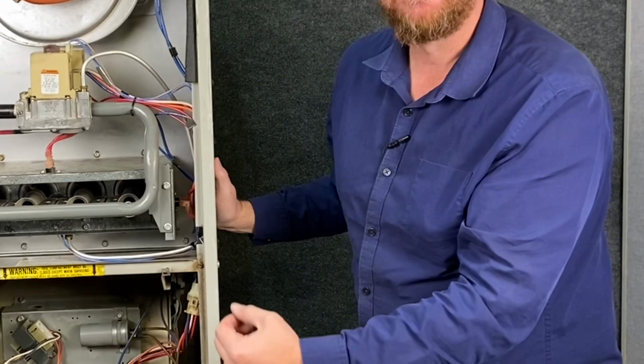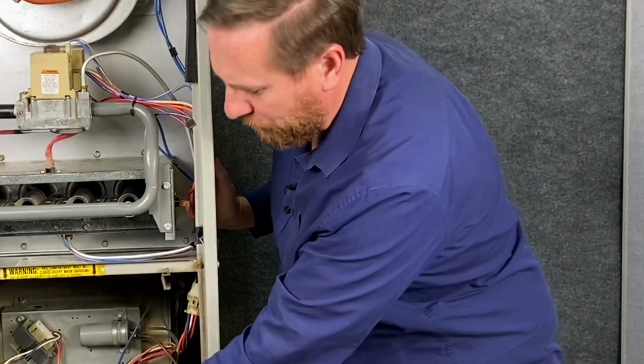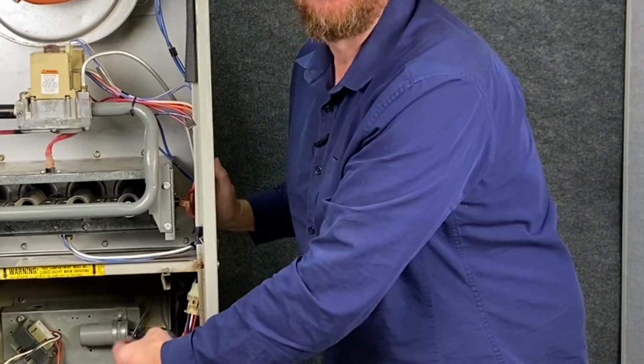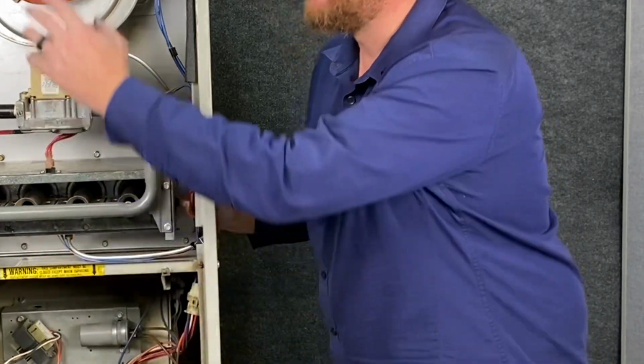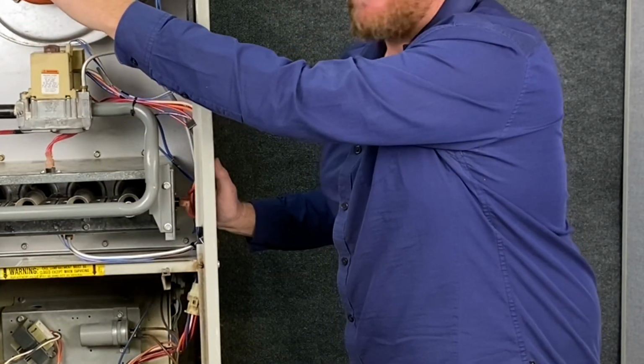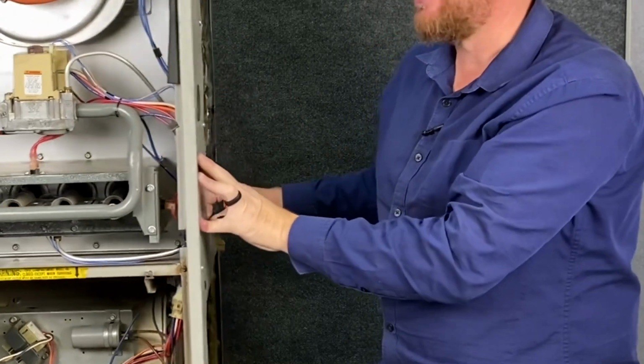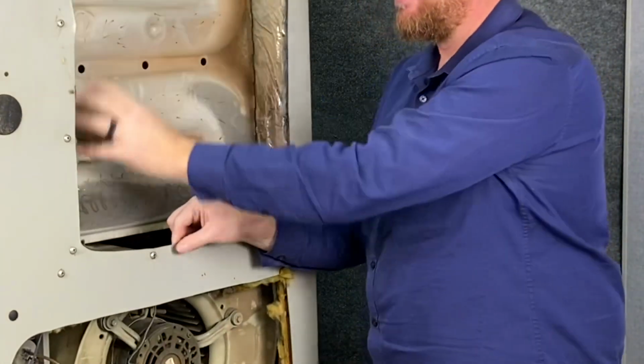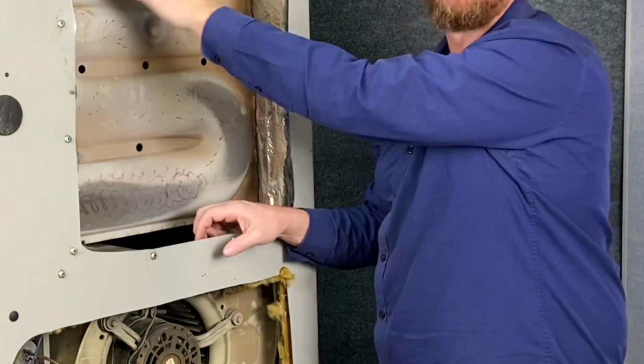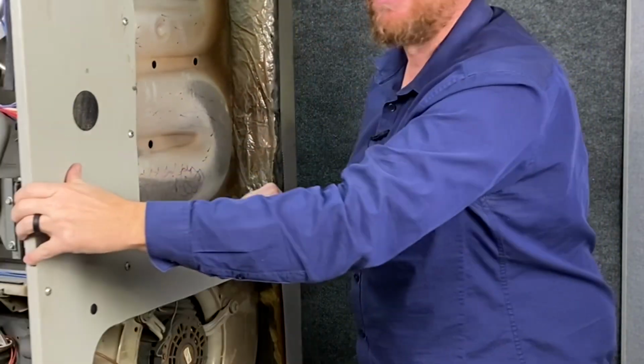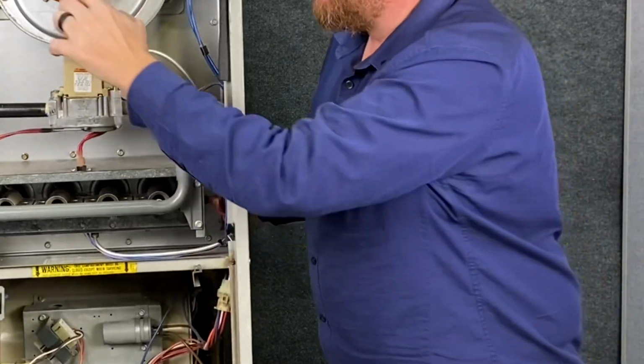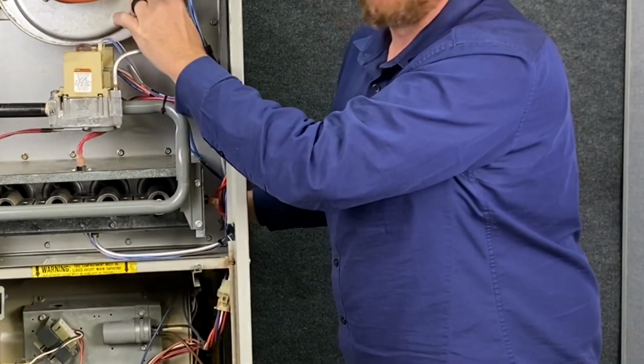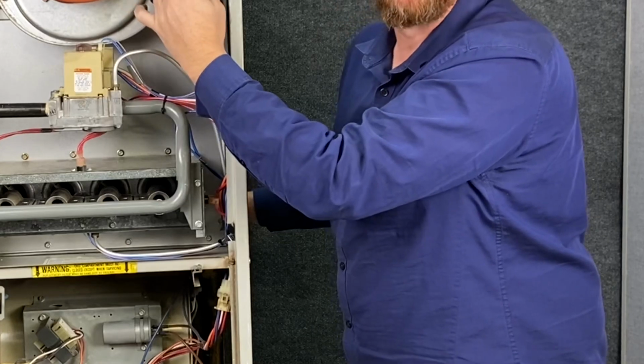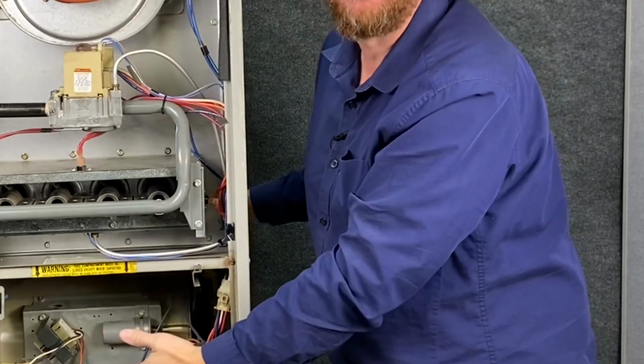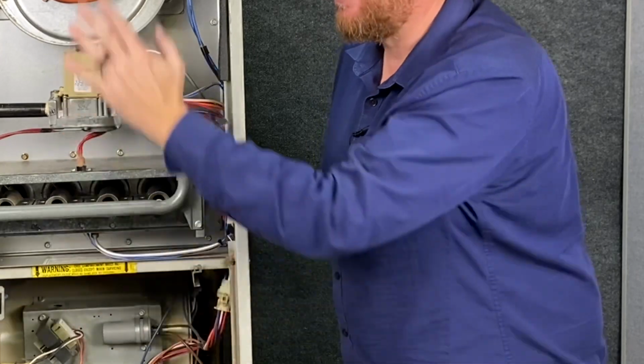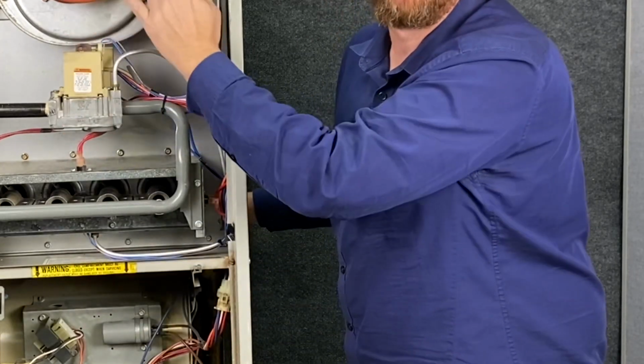The thermostat is going to call for heat, connecting R and W, sending 24 volts to the IFC. The IFC is going to do a quick safety check. The IFC is going to energize our inducer fan motor. This inducer fan motor is going to pull a draft through the heat exchanger, making sure it's clean and clear before we have an actual ignition system. Once this pulls a vacuum, it closes the pressure switch. The vacuum pulls the pressure switch closed. The pressure switch sends 24 volts to the IFC, assuring the IFC that, hey, we are working safely, this motor is running, we have the proper vacuum.